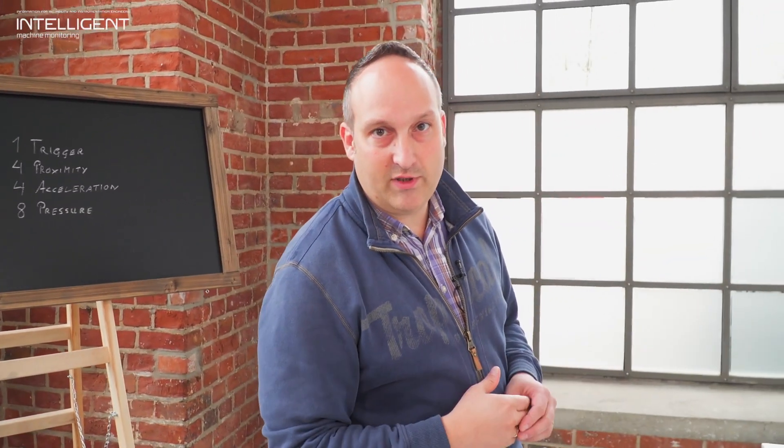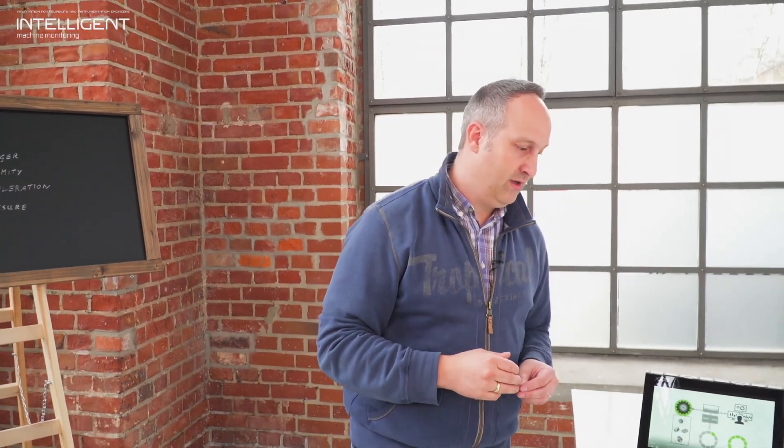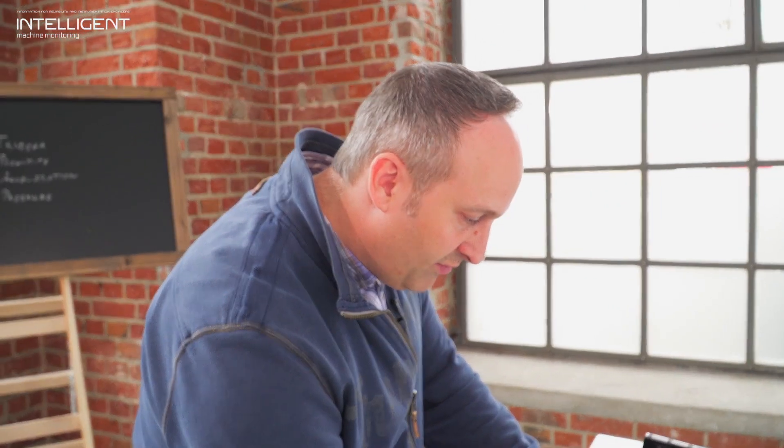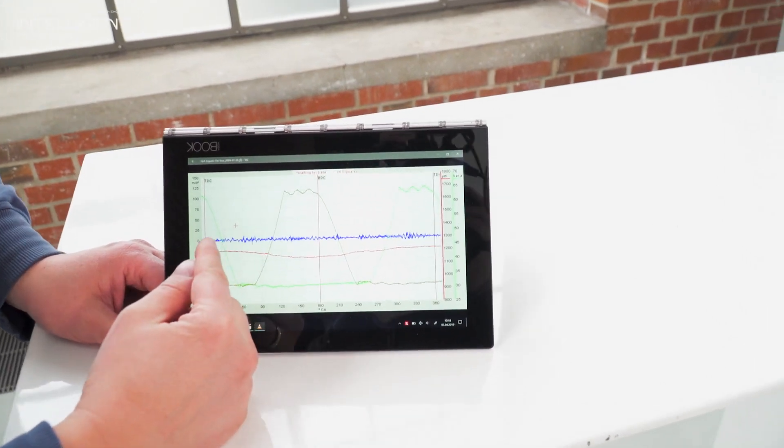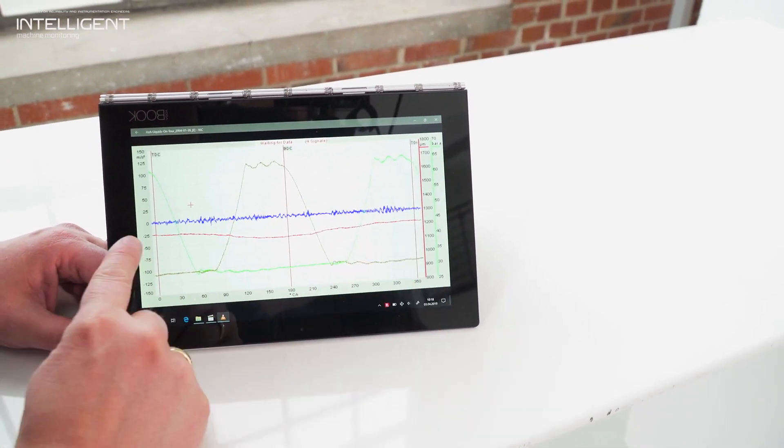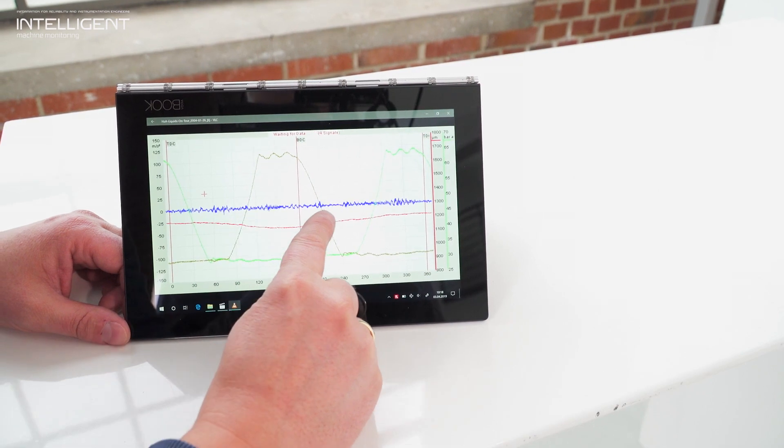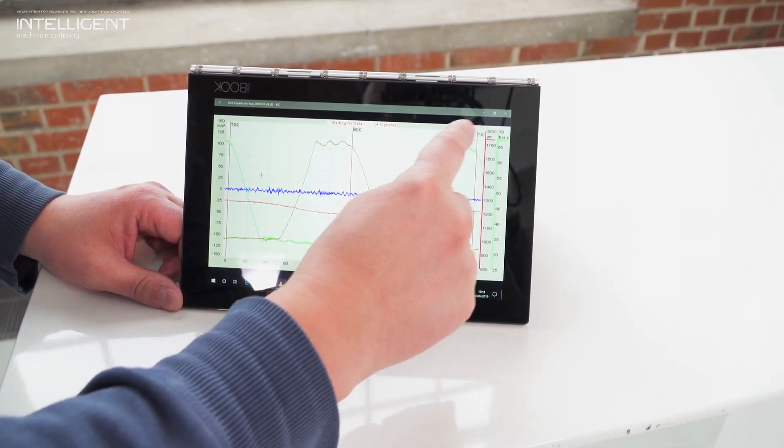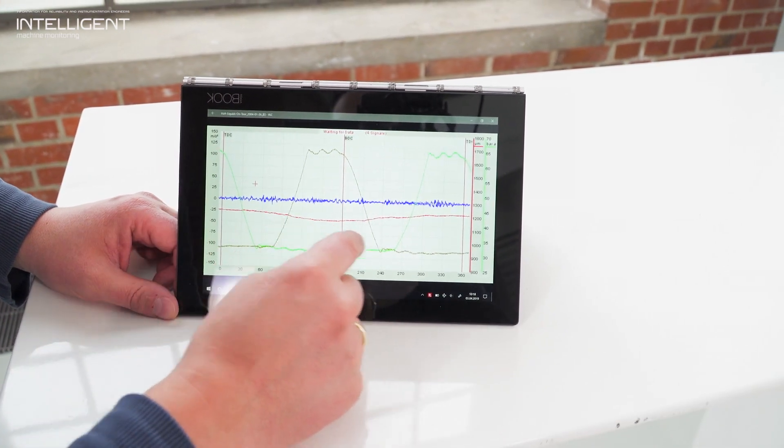The machine will run with 420 rpm. Let's start the movie which also the operator can see. You will have here the acceleration signal, the piston rod position, and also the dynamic pressure information for head end and crank end side.